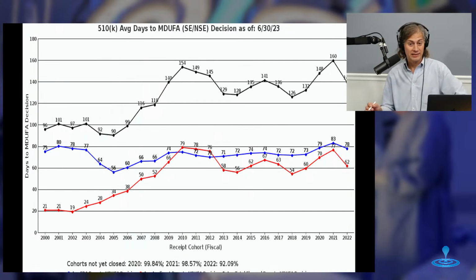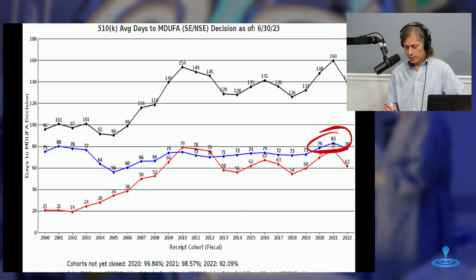So how long is FDA saying this takes on average? You saw a plot for a couple of different product codes dancing all around from 30 days to 400 days. What's the average from FDA's perspective? Well, in blue is the average days, FDA days, when their clock is not paused, to MDUFA decision. And back at the turn of the millennia, it was around 75 or 80 days. And then in COVID, it was back up to nearly 83 days. It's been hovering in that 60 to 80 day range, which is within its window, right? It's more than their 60-day goal to get back to you. It's less than their 90-day goal for the decision.